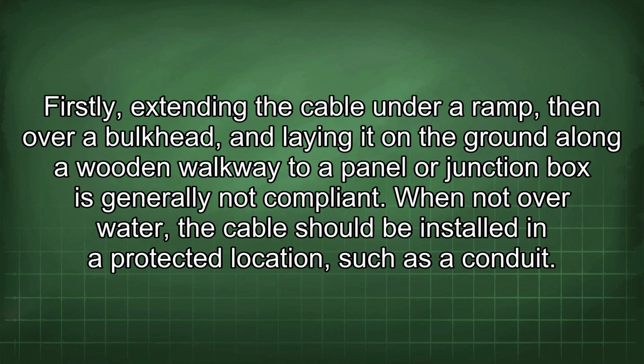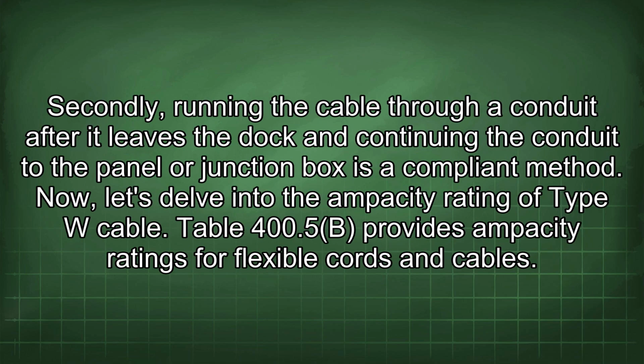Firstly, extending the cable under a ramp, then over a bulkhead, and laying it on the ground along a wooden walkway to a panel or junction box is generally not compliant. When not over water, the cable should be installed in a protected location such as a conduit. Secondly, running the cable through a conduit after it leaves the dock and continuing the conduit to the panel or junction box is a compliant method.